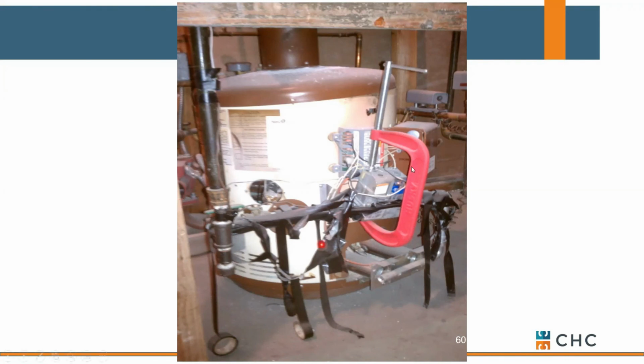And the other thing we're seeing is kind of some big budget crunches, right? We don't have a lot of money left over for maintenance or service. So when somebody needs heat, they tend to grab the biggest C-clamp they can find so that they don't have to reset their manual reset high limit every morning, okay? Because all they want is heat in their school. What they forget is they've just taken out one of their safety devices.